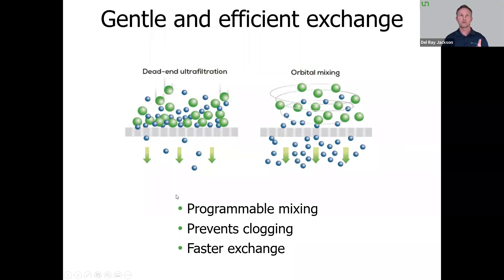Dead-end ultrafiltration is a common problem where you can aggregate proteins or get a lot of them clumping up at the membrane interface, which really hits your sample recovery. With BigTuna, using a gentle orbital mixing that's programmable — or part of those presets for your biomolecule of interest — you avoid clogging, delivering higher sample recovery. It's also a way to get faster exchanges done, which is critical for something like LNPs. These aren't things that you would get with other techniques like vacuum filtration or centrifuge filter plates.